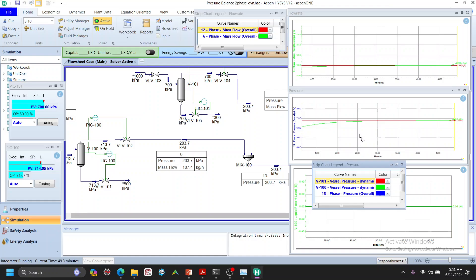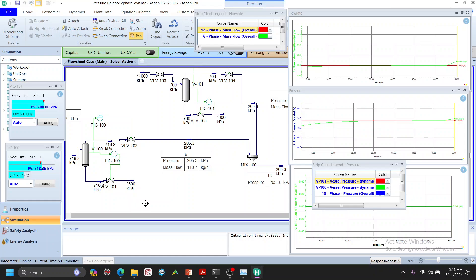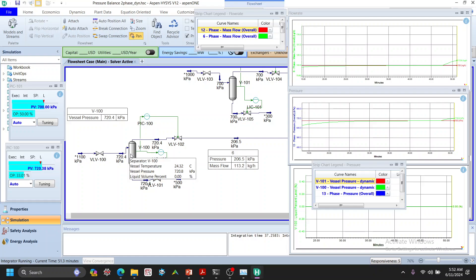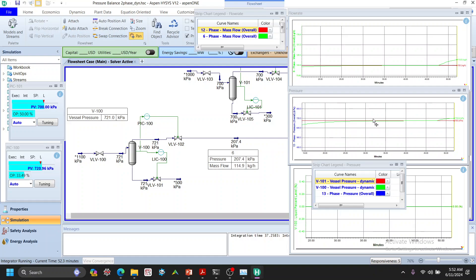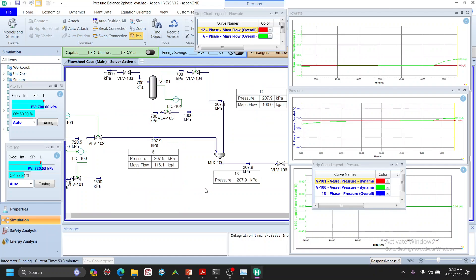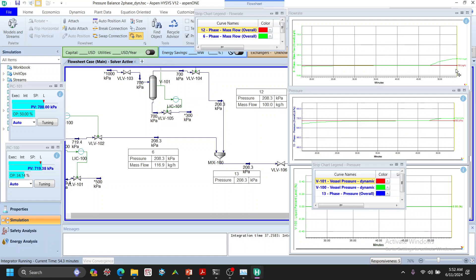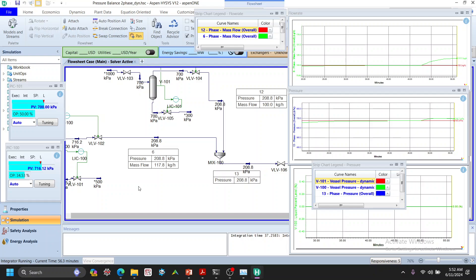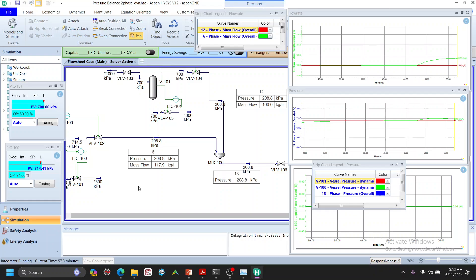We can see the pressure in the green line on the bottom graph increases as expected — higher source pressure means more gas entering, so vessel pressure goes up. The flow rate through that stream increases accordingly. However, the flow rate from the other vessel stays constant, as you can see. The controller for that one is working well — not much change there.